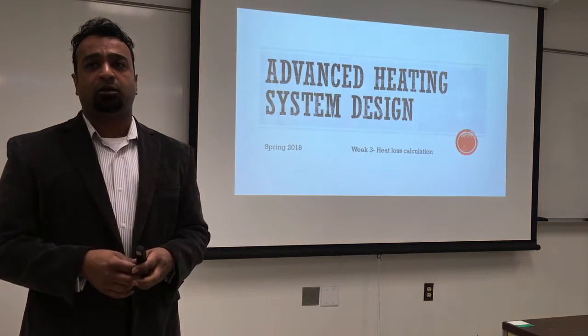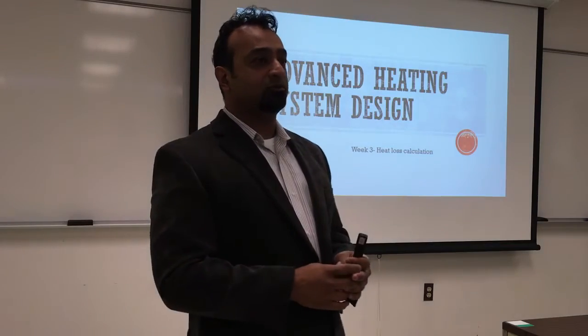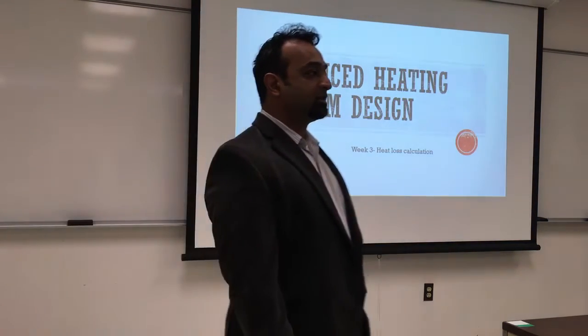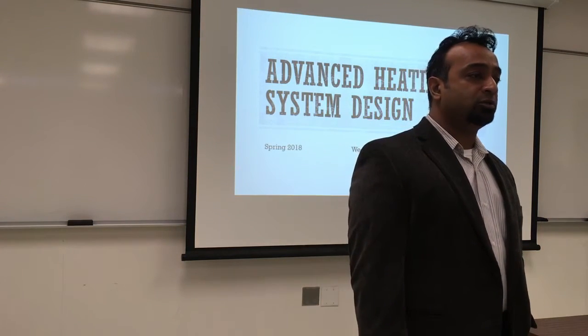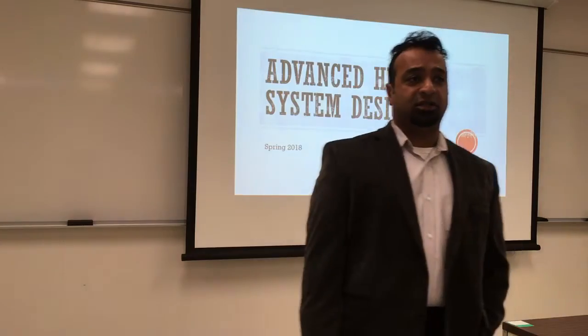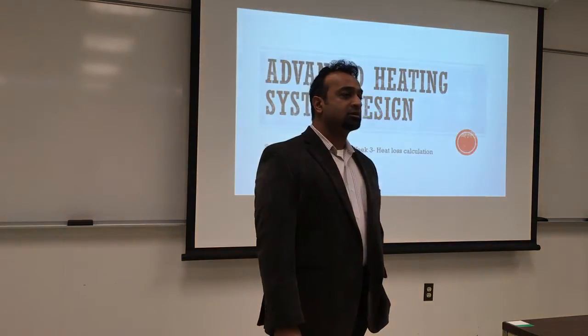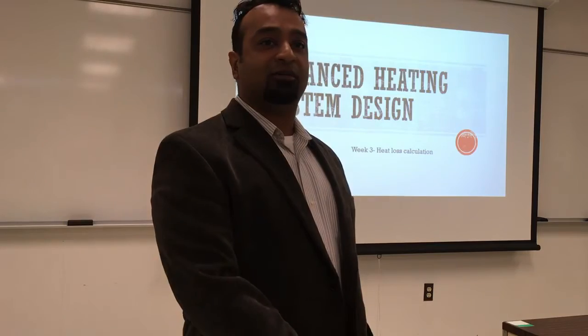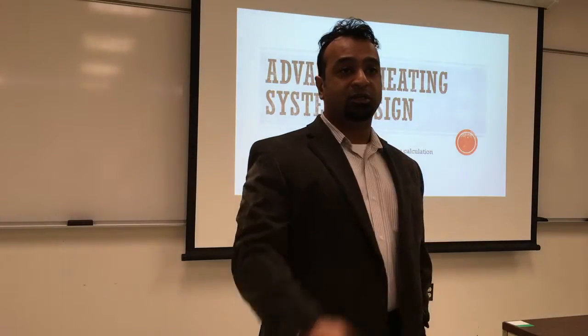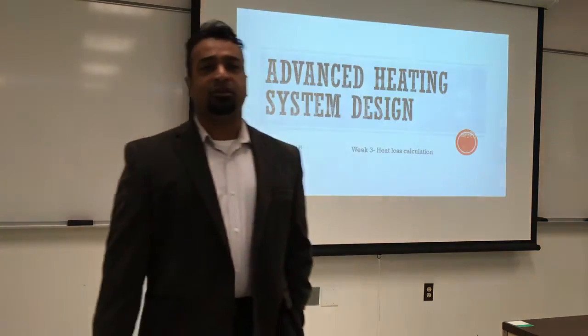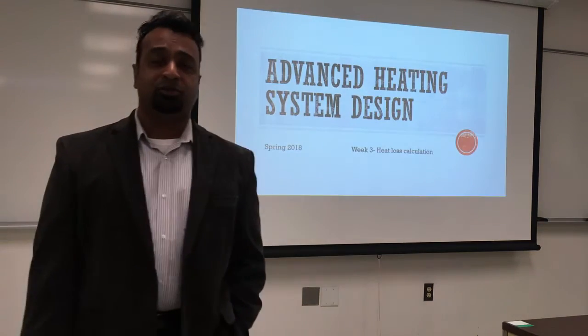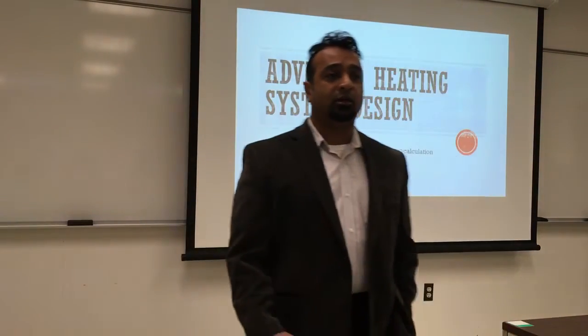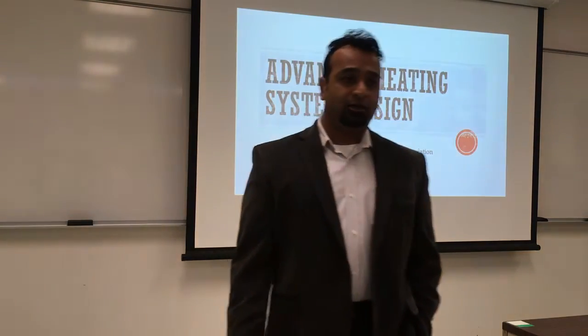I've put together the seven steps of performing a heat load calculation according to the IBR book. There are also a few software programs on the market where you fill in the material and sizes and it does the calculation for you. But I want you to know how to do this by hand using an Excel sheet, so you can account for little discrepancies—like a wall that's half covered, a roof that's partially heated, or a wall retrofitted with new insulation.